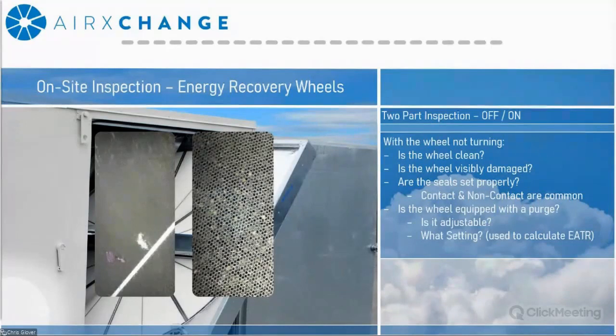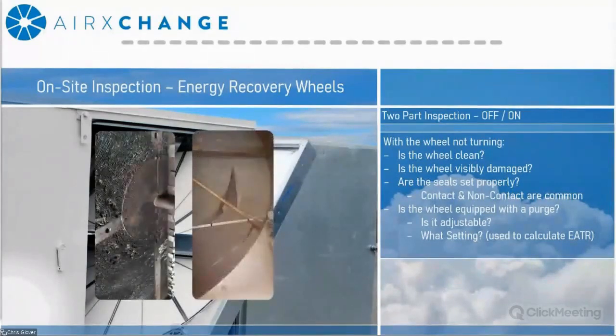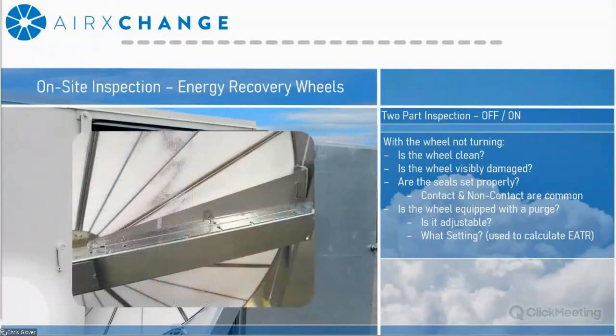So you'll see dirt or debris on the media. You can see visual gapping or bridging that may be occurring on the heat exchanger. You also want to look for any potential damage. You look for pieces of section that are missing or any structural components that have corroded or may be compromised over time. Typical damage would be significant corrosion or pitting. So, to give an example of that, you can take a look at the pictures. These are things that are usually pretty apparent, but can be overlooked if you're not at the unit looking at it properly.